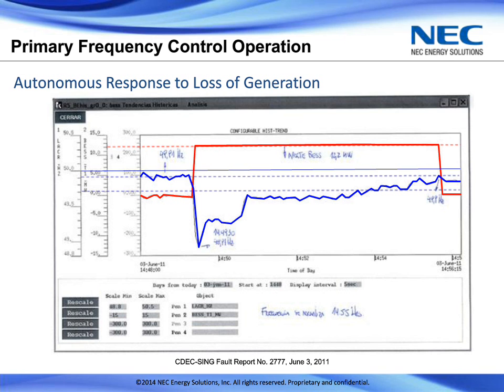Now, one thing to note about this strip chart is that it's not registering the changes in power fast enough to show how fast the BESS actually responds to the loss in generation. In fact, even though you can see a slope on the red curve, the actual slope is nearly vertical. The response times of these systems are under 250 milliseconds and can respond very quickly from full discharge to full charge. So that 12 megawatt system I showed before could go from a negative 12 megawatt charging to positive 12 megawatt discharging, so a full 24 megawatts of ramp rate well under a second.